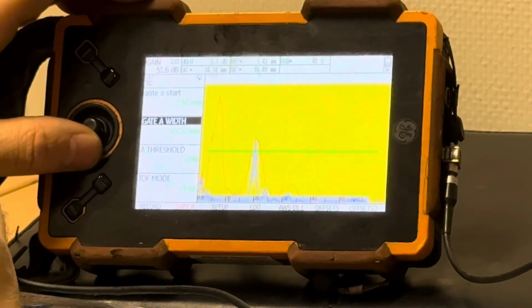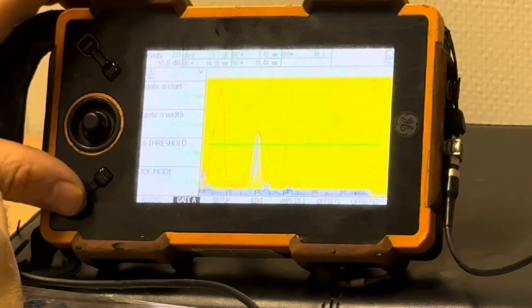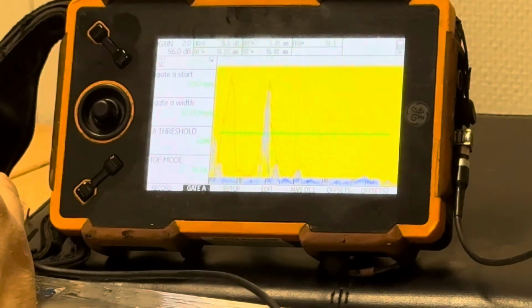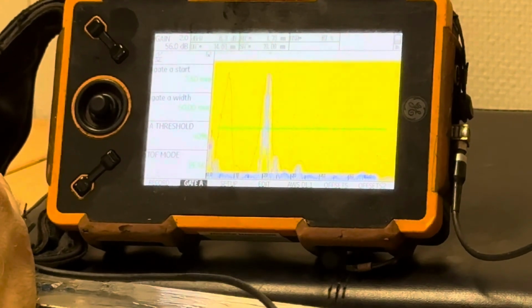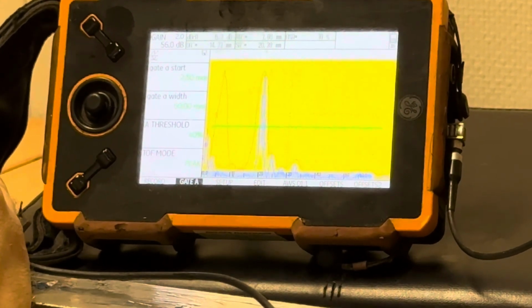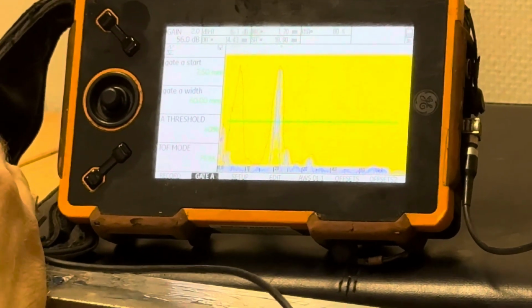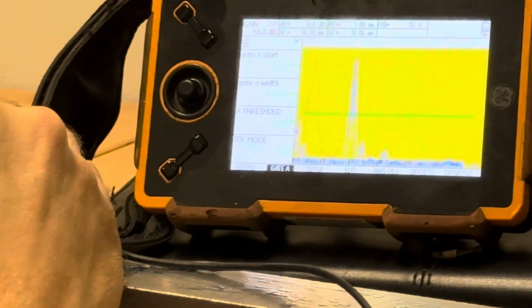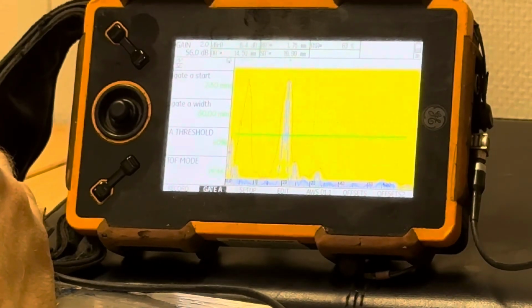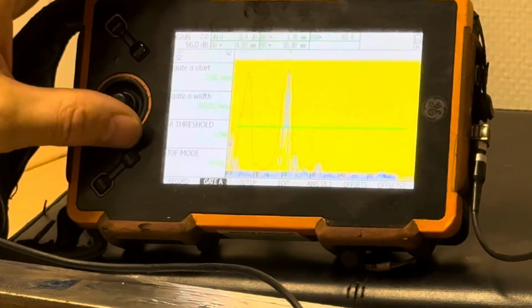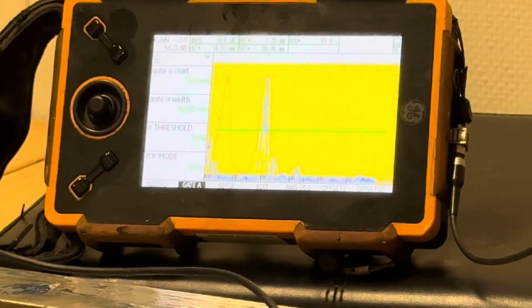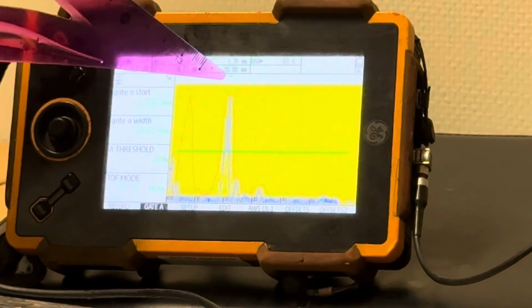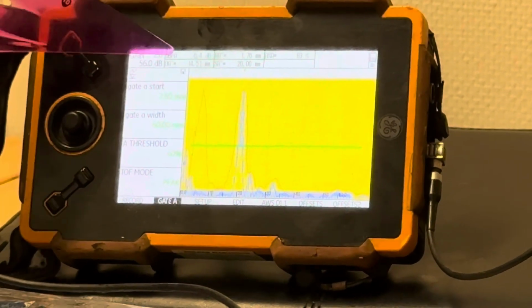Okay, now, let's make the gate wider. Let's set it to 80% of the monitor's display area. Then we find the absolute maximum value. We will then turn it gently left and right. Again, we find the maximum. Next, we check what specific kind of signal this is. The green marker indicated by the arrow clearly shows that it's accurately catching this exact signal, not some other one. And it shows a depth of 14.5 millimeters.